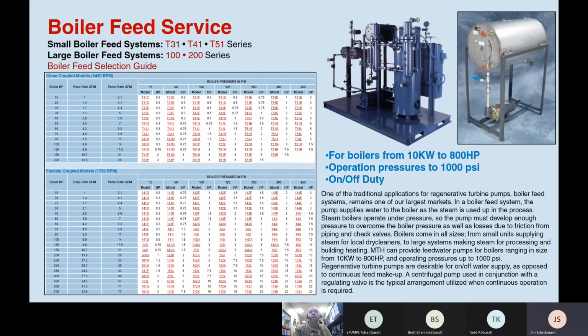Boiler feed service, like I had mentioned: we overcome the pressure of a boiler system in a building because of our high pressure, and we can refill a boiler using our pumps. We have a full boiler feed selection chart on our website, which lets you look at the boiler horsepower. It calculates the evaporation rate and the pump rate, the GPM needed to refill that boiler, and then selects the pump for you at whatever the pressure is in the boiler. So it's a handy tool if you're replacing a boiler.